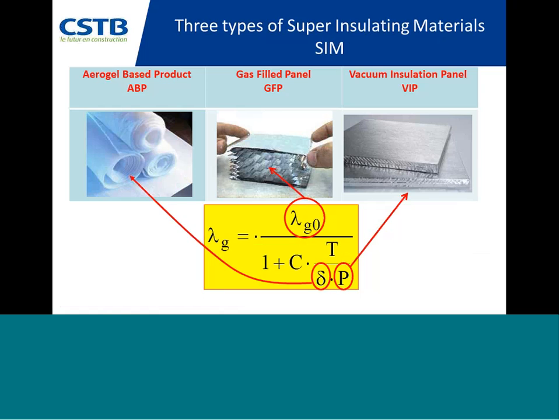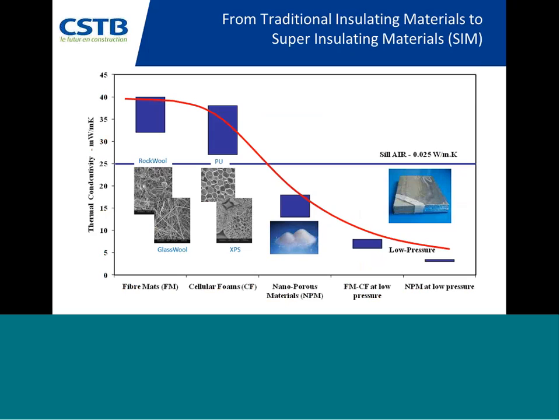Right now on the market there are three types of superinsulating materials using one of the three options: nanoporous materials like aerogel, using the decrease of cavity size; vacuum insulation panels (VIP), using the decrease of pressure; and gas-filled panels, which are not widely used — these are like a cellular structure using another gas than air, similar to double glazing with argon or another gas. This slide shows a whole range of available thermal insulating materials.